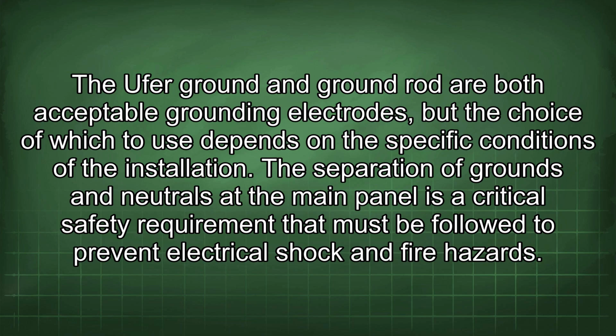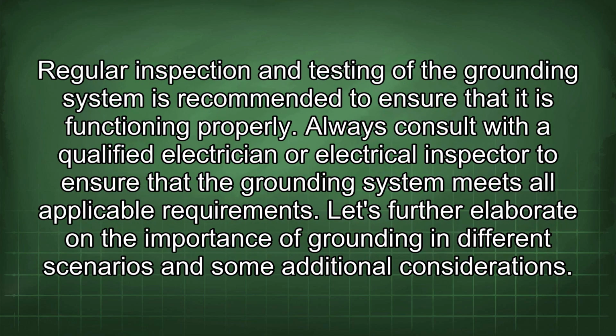The separation of grounds and neutrals at the main panel is a critical safety requirement that must be followed to prevent electrical shock and fire hazards. Regular inspection and testing of the grounding system is recommended to ensure that it is functioning properly. Always consult with a qualified electrician or electrical inspector to ensure that the grounding system meets all applicable requirements.